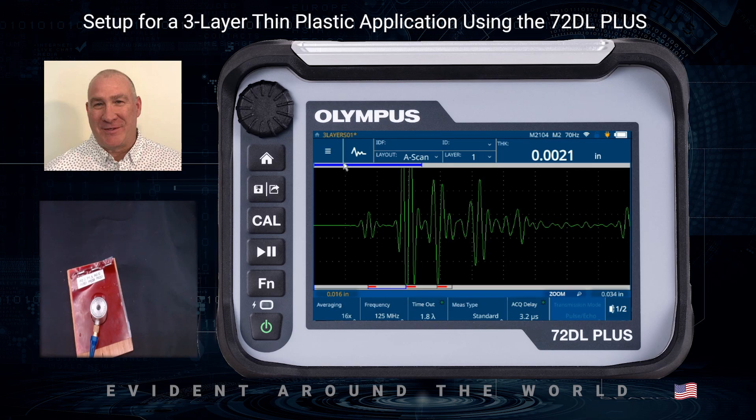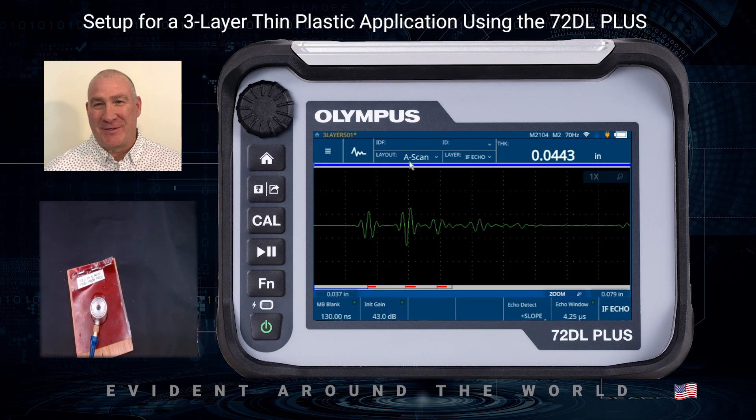That looks pretty good. What I have here is a three-layer material: this first small echo is the reflection off the front surface, then the reflection off the first layer, the second layer, and the third layer. I want to set up my echo window — the main bang blank echo window — so that I'm looking at just the echoes in this area of interest. I'll click on the Wave Adjust icon and select 'Interface Echo' from the drop-down. I'll click on Main Bang Blank and use the adjustment knob to set it just before those echoes.